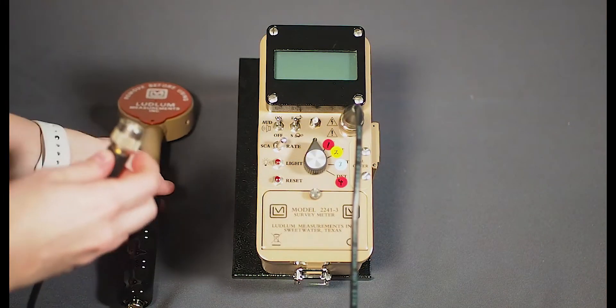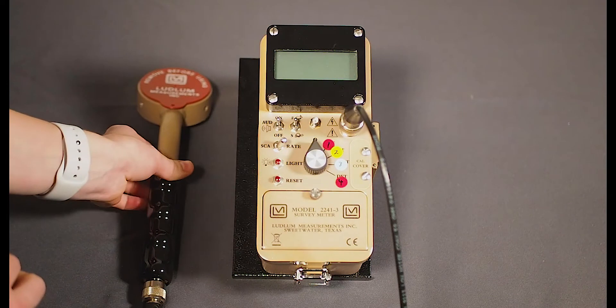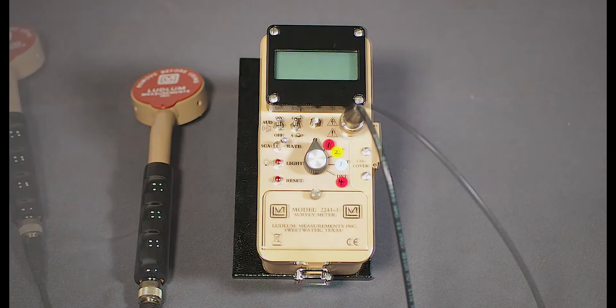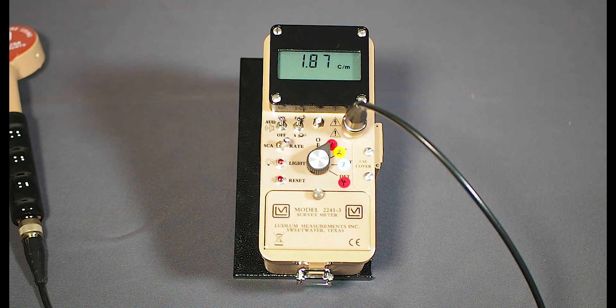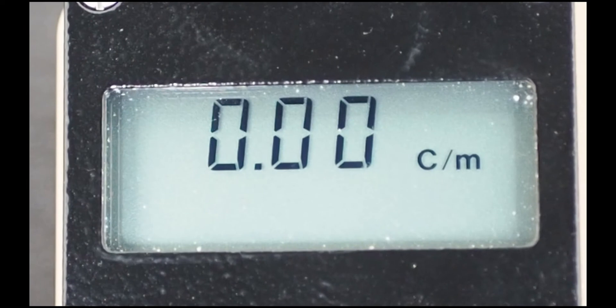Connect the C cable to the Model 2241-3 and connect the other end to the 44-9. Turn the rotary switch to the detector one position. The instrument will go through a quick boot up process. Ensure the low battery symbol is not displayed. If it is, replace the batteries.